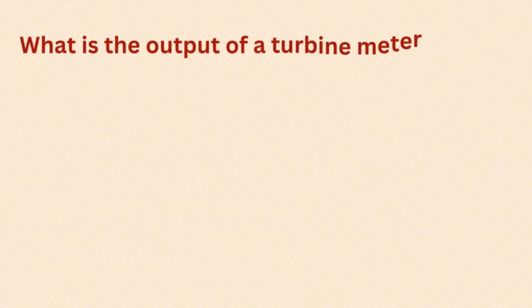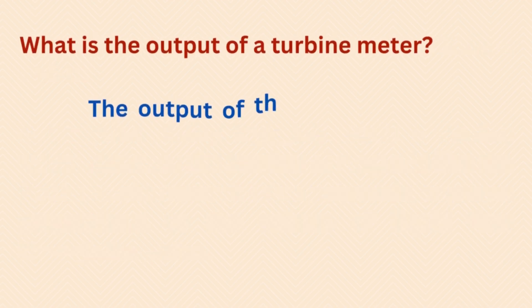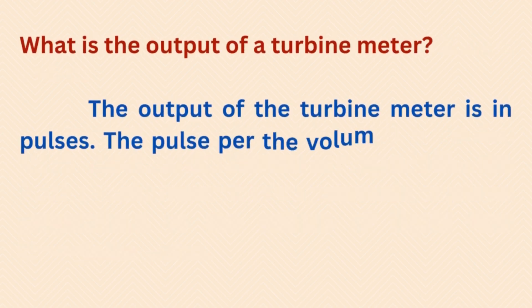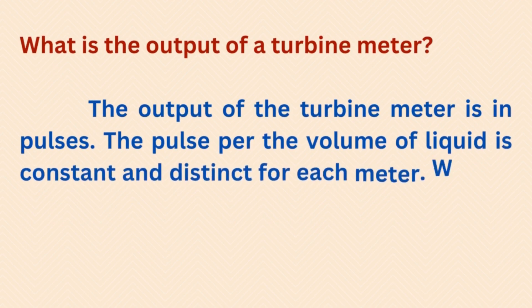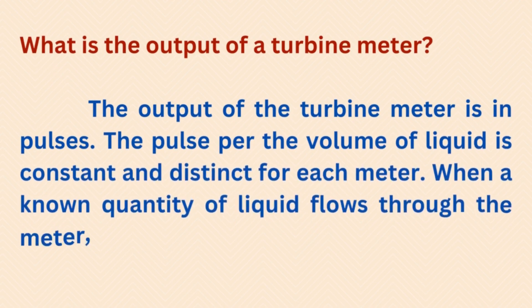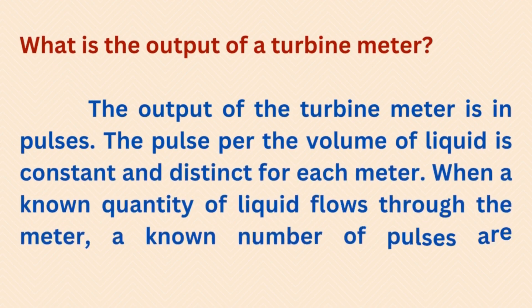What is the output of a turbine meter? The output of the turbine meter is in pulses. The pulses per volume of liquid is constant and distinct for each meter. When a known quantity of liquid flows through the meter, a known number of pulses are produced.